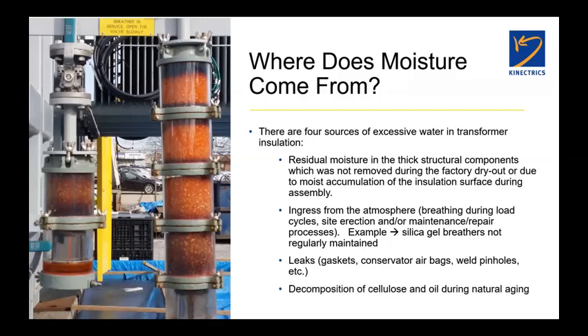And then again, the one that we don't often think of, a little bit more nefarious, more hidden, is that the normal, and I want to emphasize this, the normal decomposition of cellulose paper during the natural aging of a transformer produces water. So even a transformer that doesn't have leaks, doesn't have issues with the silica gel breathers, sooner or later is going to manufacture, if you will, its own moisture inside itself, and so its moisture content will start to rise.